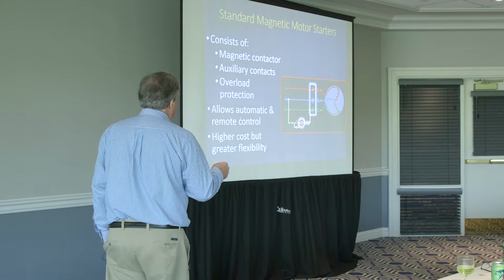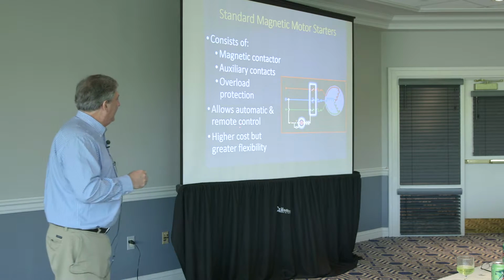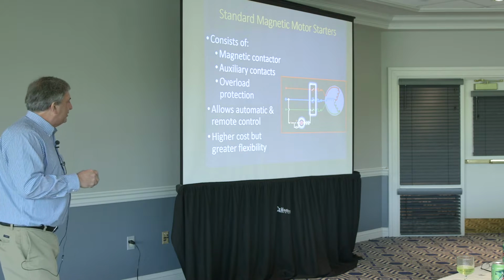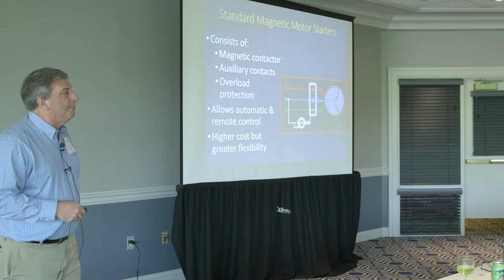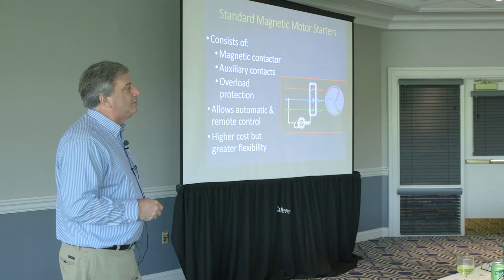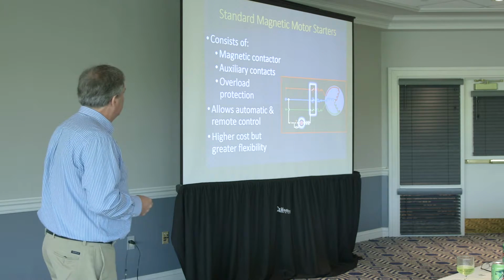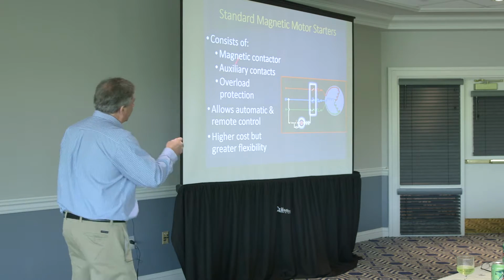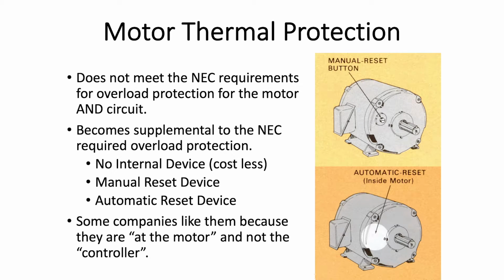Okay, so that allows automatic and remote control, which we like. Higher cost but greater flexibility than a manual motor starter that the code lets us use on a small motor. Okay? So we've got those types of things. Now, one of the questions I get a lot is, why does the National Electric Code make me have overload protection at the starter if I have a motor that has overload protection at the motor?